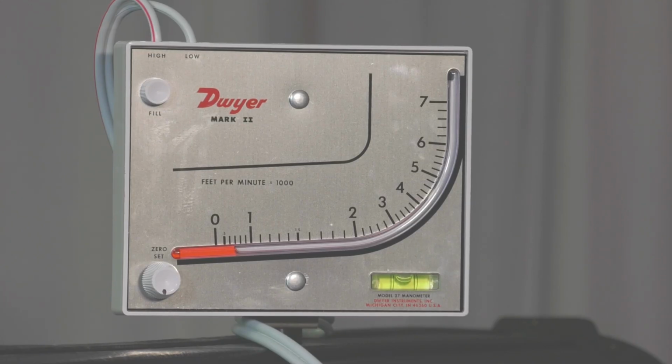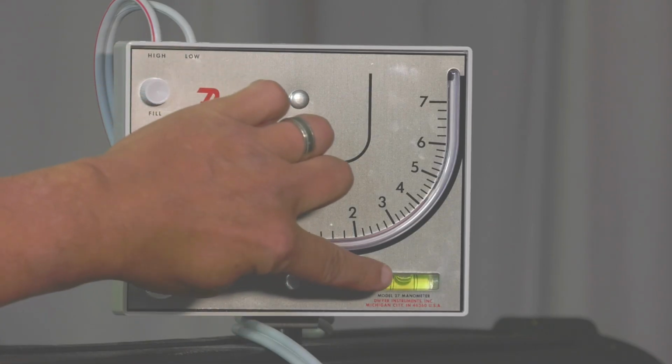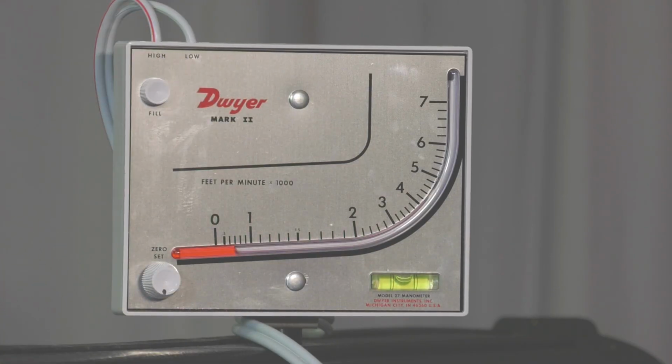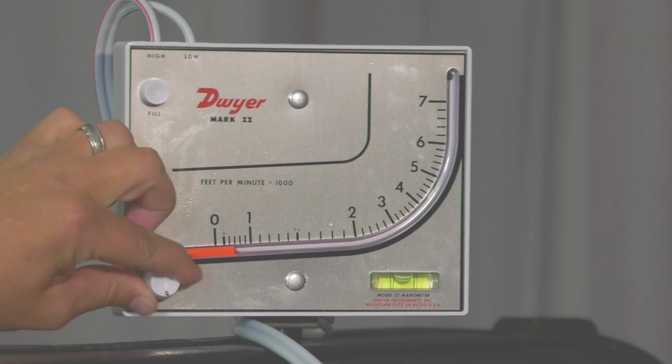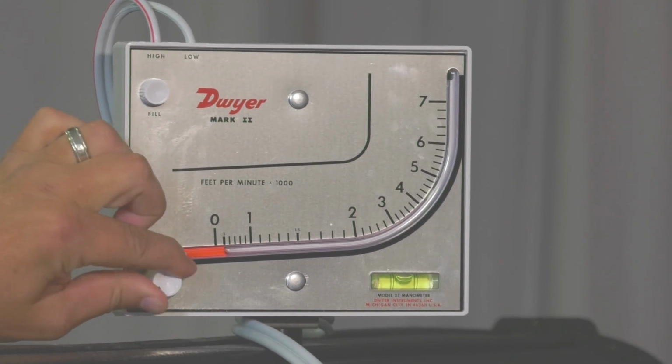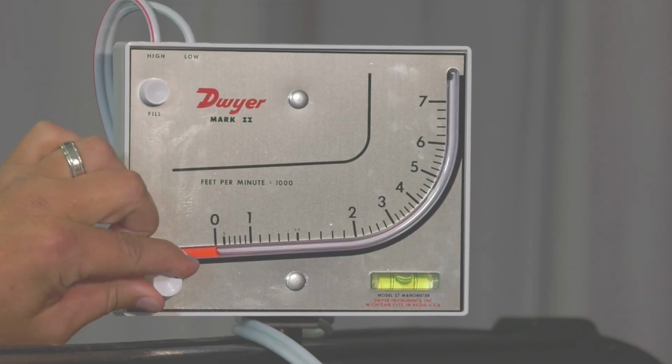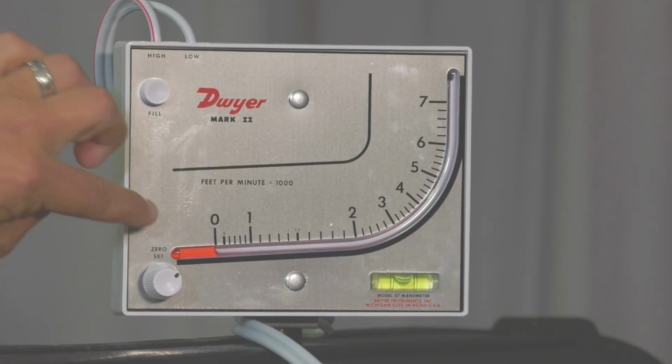So before we take data, one of the first things we want to do is to calibrate our instrumentation. Here we're going to calibrate our manometer, which measures the speed of the air in the wind tunnel. First, we ensure that our manometer is level so that the fluid levels here are not skewed by the manometer being not level. Then we use the 0 setting here to adjust this fluid level until it reaches a 0 value, doing our best to approximate that line of 0 with the meniscus of the fluid.